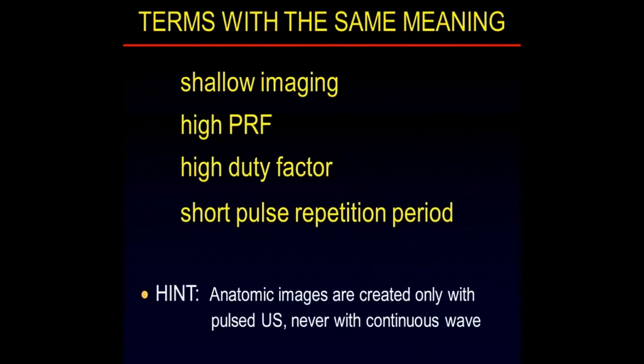So listen to this. This is important. Shallow imaging: high PRF, high duty factor, a high-ish percentage of time the machine's talking, and a short pulse repetition period, a short time from the start of one pulse to the start of the next pulse. Those things are synonyms. You have a chart in your book that says how you can describe shallow imaging, 4 different ways, and how you can describe deep imaging, 4 different ways. Know that list.